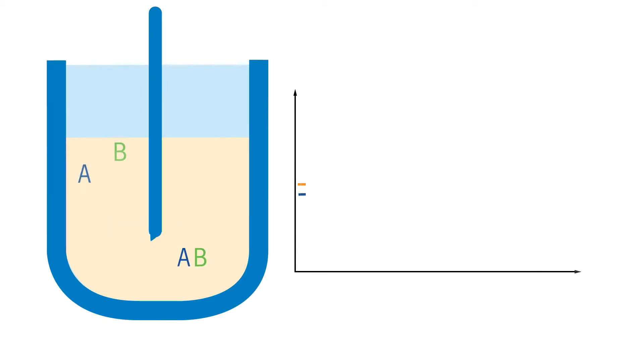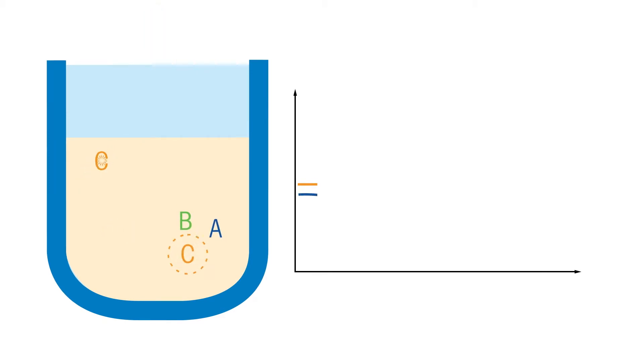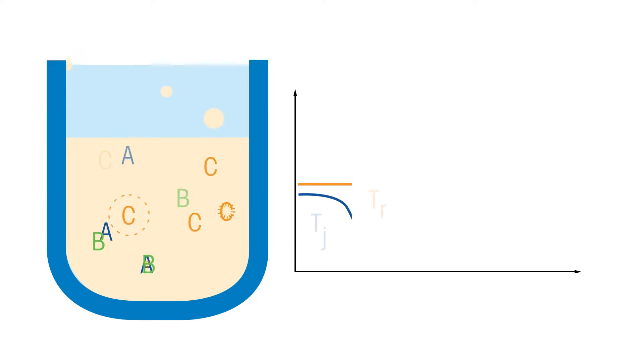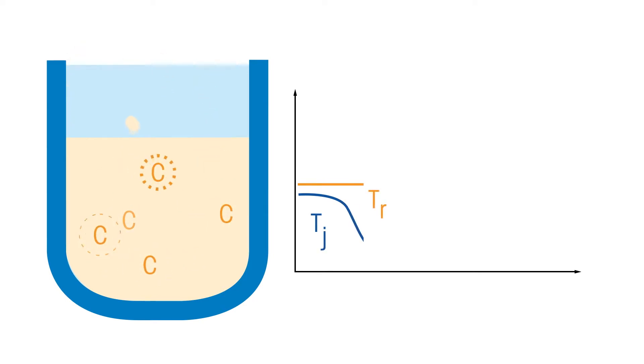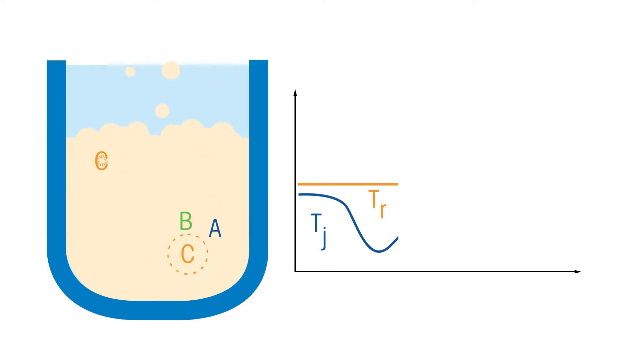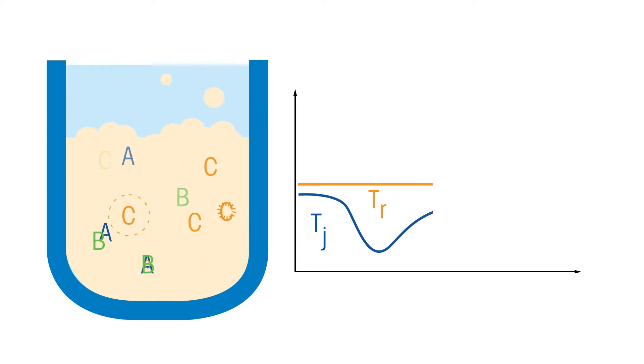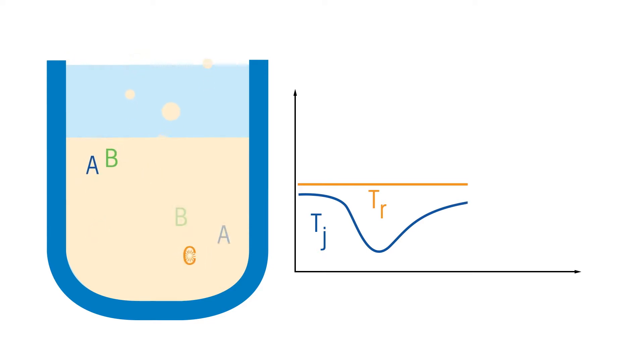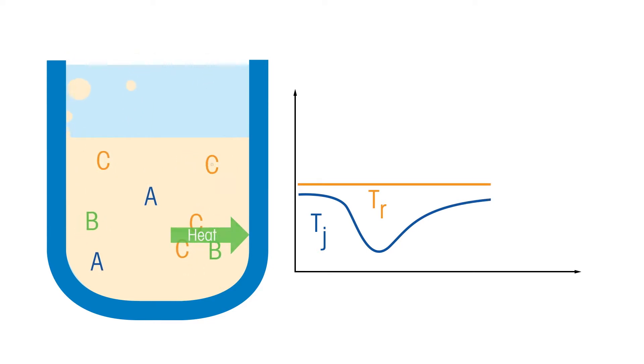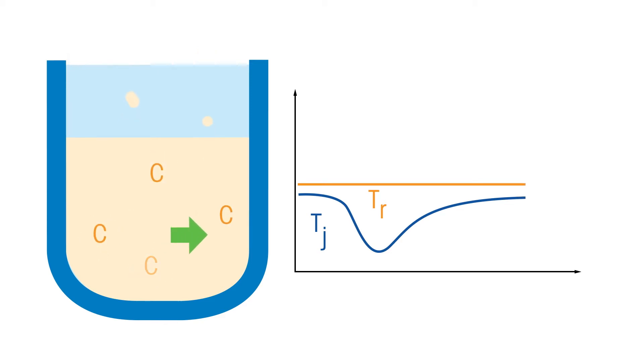When reactants are converted into product, heat is released in most cases. In order to remove the heat produced by the chemical reaction efficiently and to maintain the temperature at its desired set value, the temperature of the surrounding media needs to be adjusted accordingly, forcing the released energy to flow across the reactor wall into the heat transfer media.